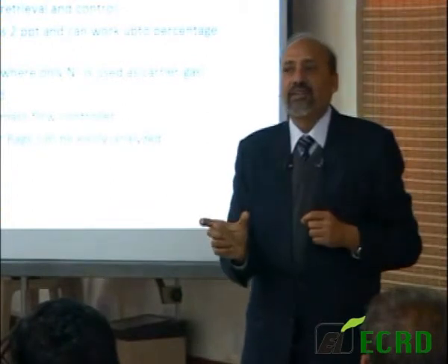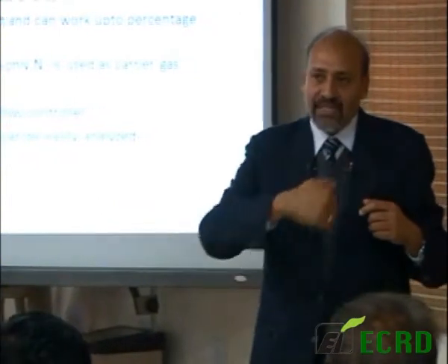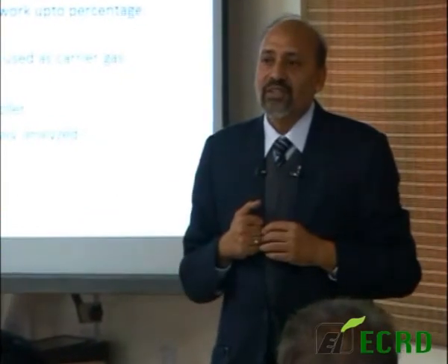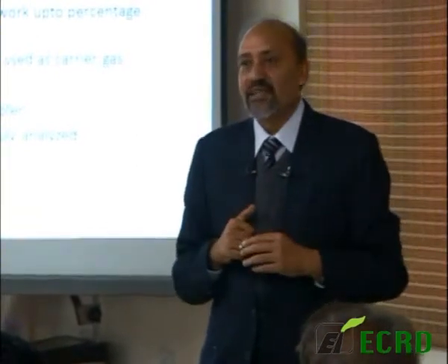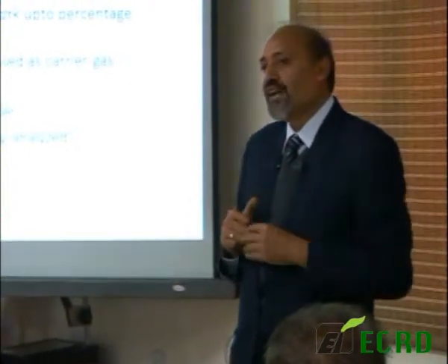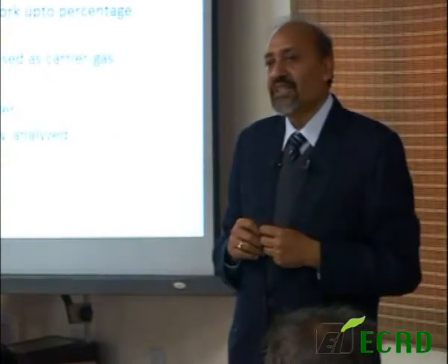So they just take a direct air sample. They've got a small Tenax trap inside the GC system, which initially collects over a 15-minute cycle the benzene or whatever organic pollutant you're trying to get, just like our organic vapor sampler does. And then for the next 15-minute cycle, it switches over to a purge from nitrogen, and at that time they are heating this trap up to 250 degrees centigrade. The temperature rise is controlled by the PC itself, and at that time they are injecting out what is coming out from this trap into the capillary column for GC analysis.